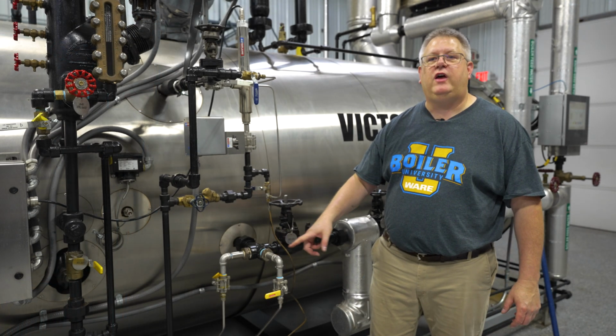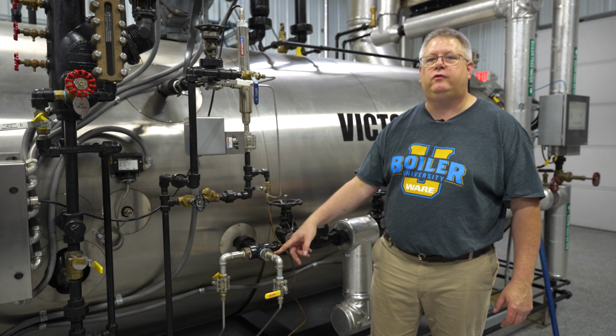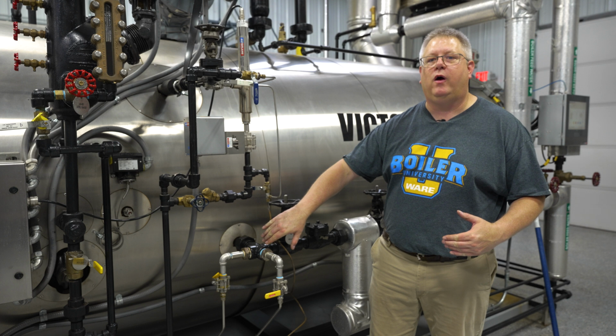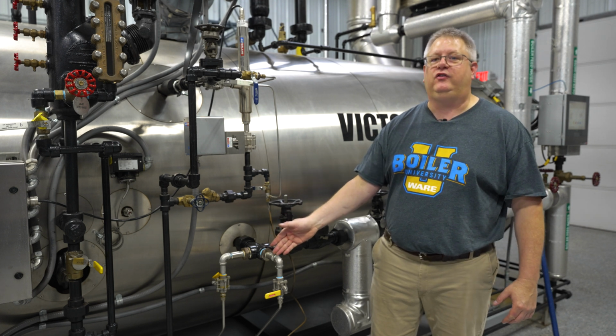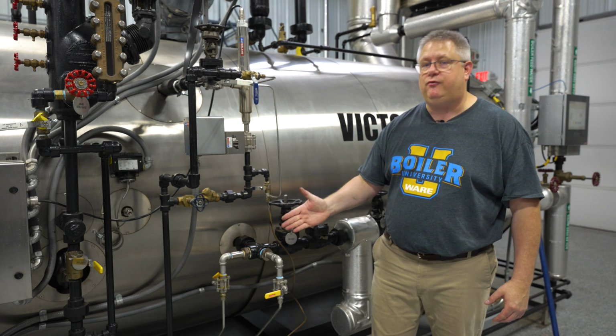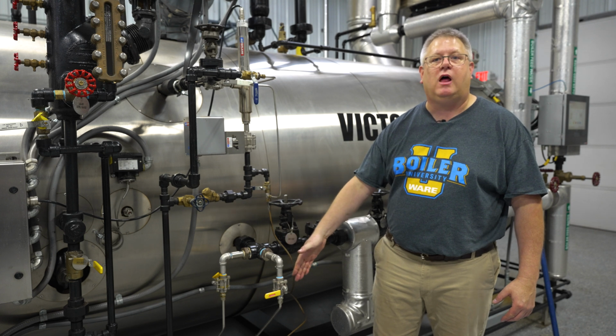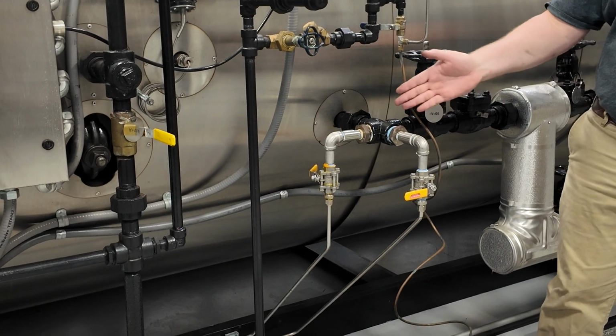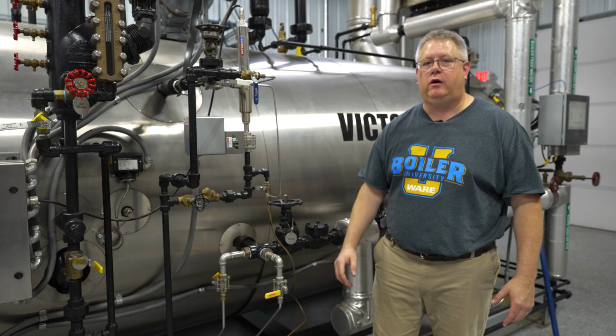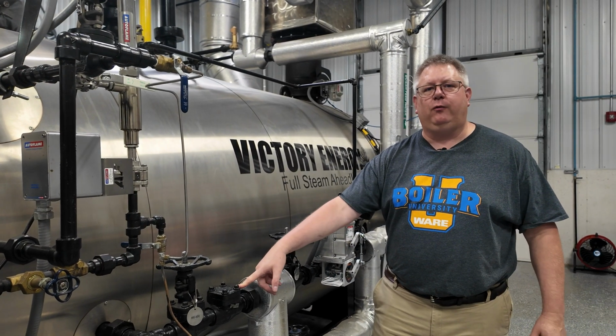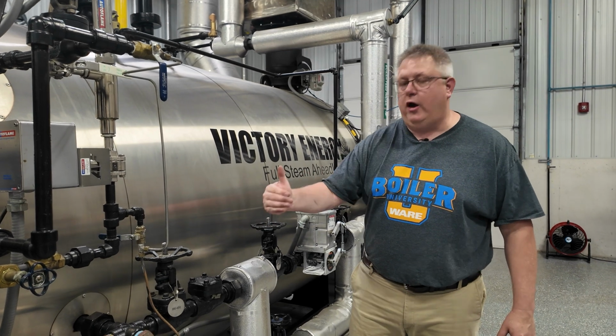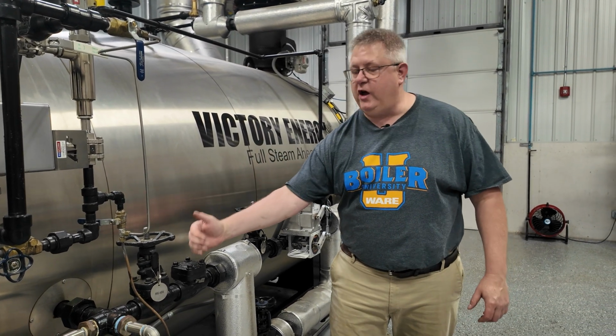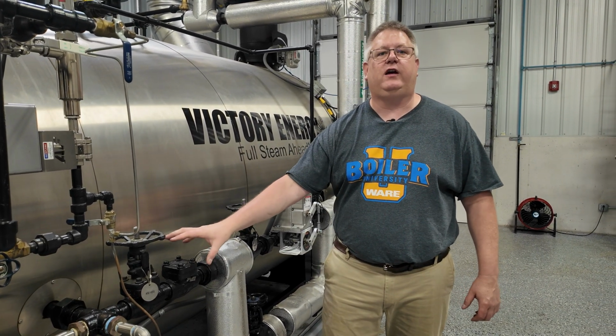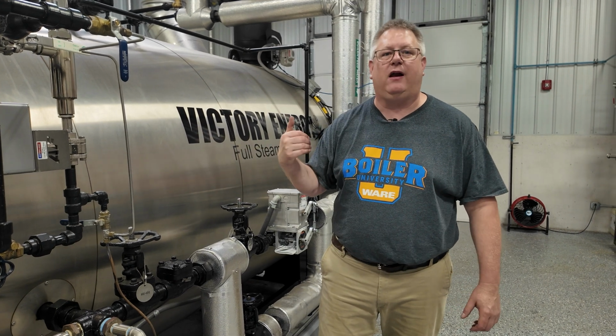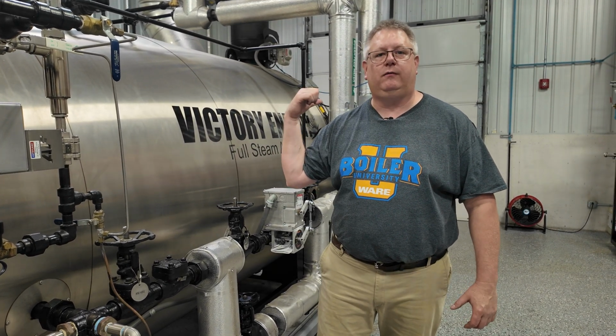Many of our chemical injection points use quills to inject chemical into the boiler, and they often include a check valve mechanism so that if we have a break in a chemical line or no pressure coming from the pump, we don't backfeed hot boiler water into the chemical system. Check valves are critical on our feed water inlets because if we've got an on-off pump cycle, we're 100% dependent on this check valve to keep water from flowing back out of the boiler into the feed system.